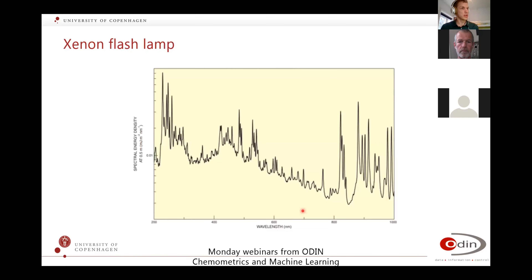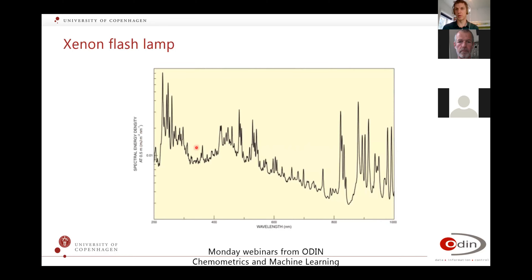What would be perfect would be a light source that is uniform throughout all the wavelengths you want to measure — but this does not happen. A xenon lamp is one of the better ones with the most stable output across different wavelengths. As you can see, from 200 nanometers to 1000 nanometers, it is quite spiky. Of course this doesn't matter so much if you correct your spectra nicely when measuring, because you know that for example 220 nm is way more intense than 400 nm, and you correct for this based on the light source profile.